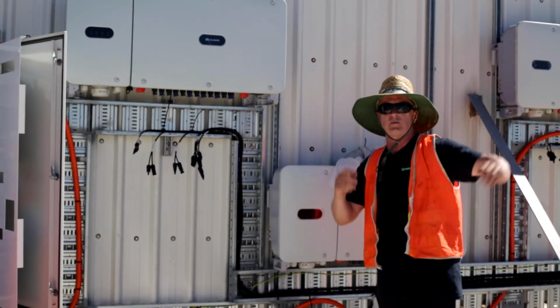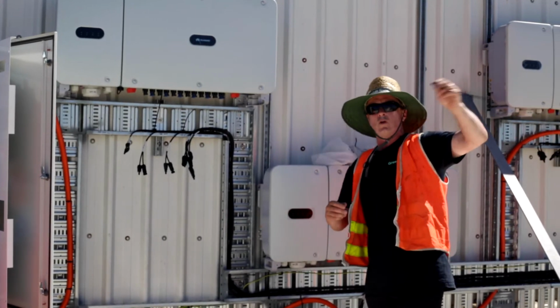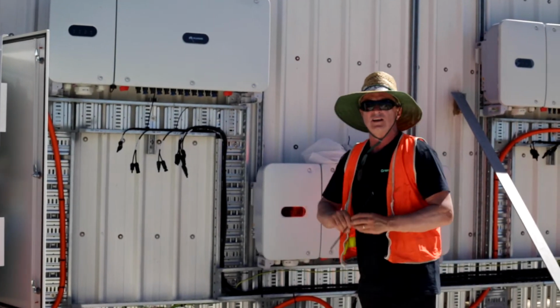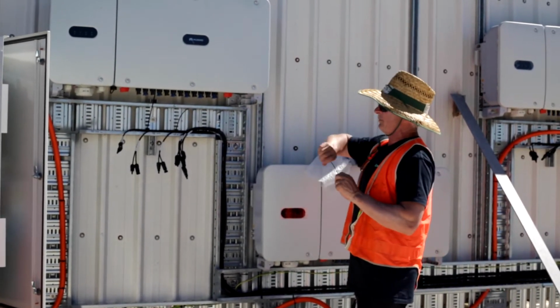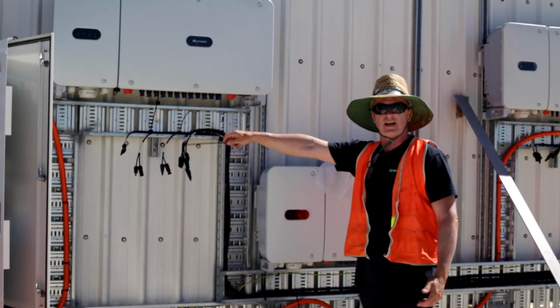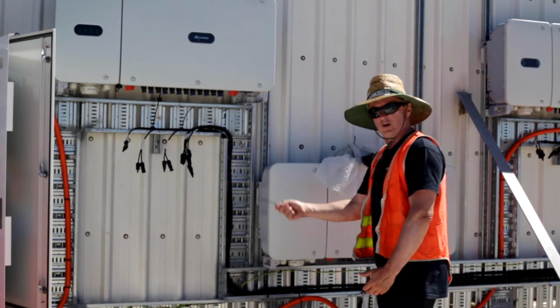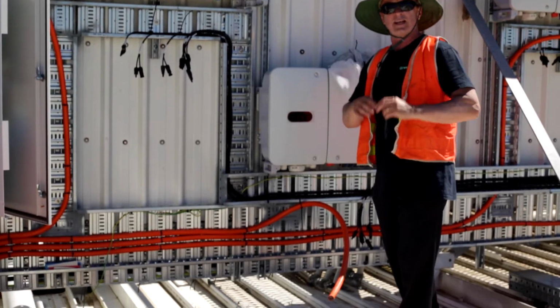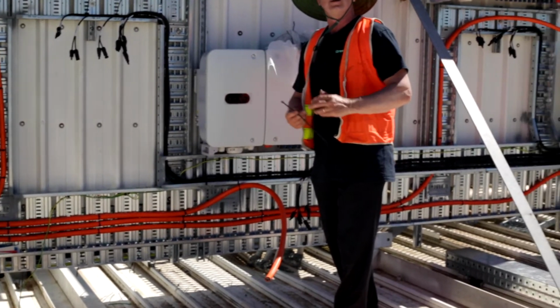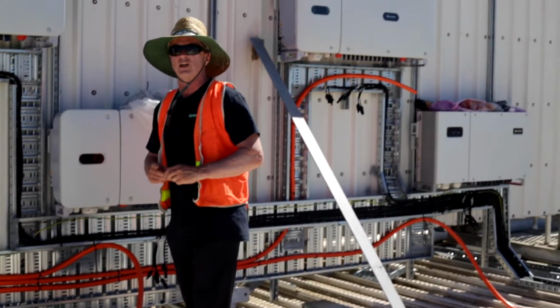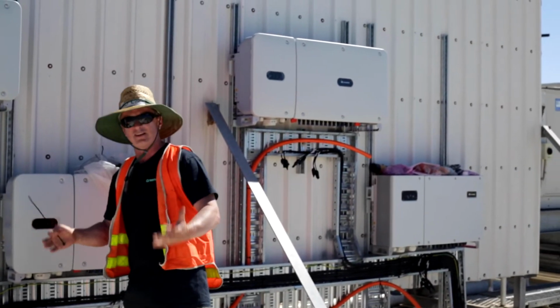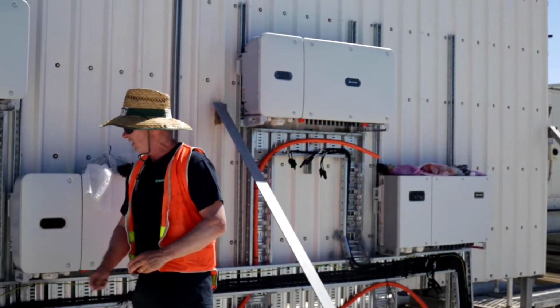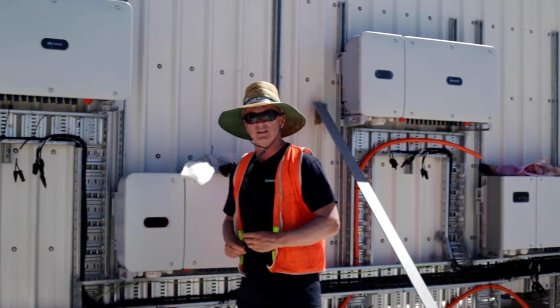Remember, volt rise is from the point of supply all the way to the main switchboard, from the main switchboard to the PVDB, being the grid safe secondary protection board, then to the inverters. Each run has to be calculated for the voltage rise situation, and of course taking into consideration the current carrying capacity of the cable, which is a separate calculation.